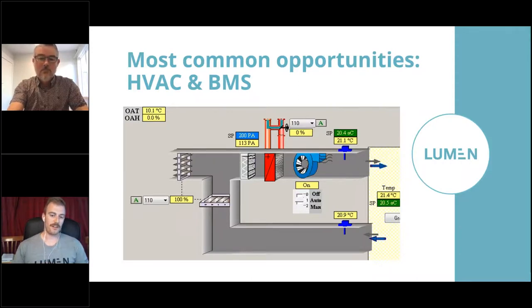It's interesting to note though that the temperature in the space is 21.4 degrees and the set point's 20.5. So if there was someone in that space, they wouldn't actually notice and they'd be having a pretty good time. So unless you're reviewing this stuff regularly, you're not necessarily getting complaints for this stuff and you won't pick it up.